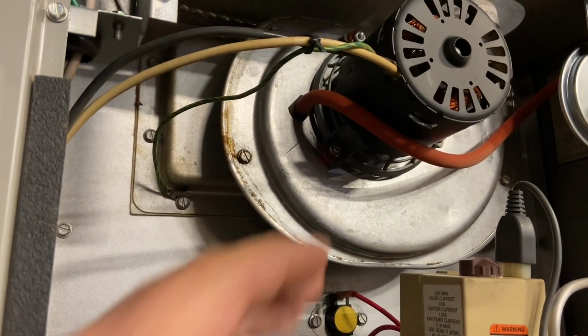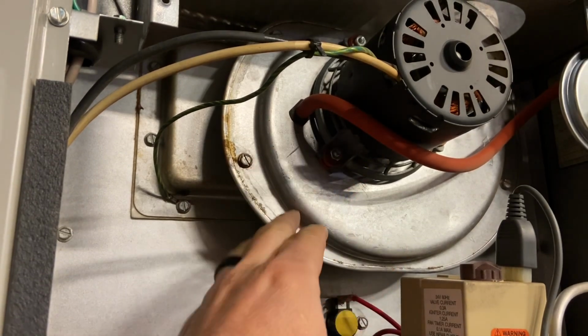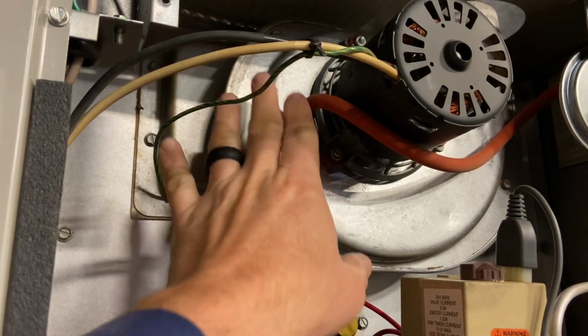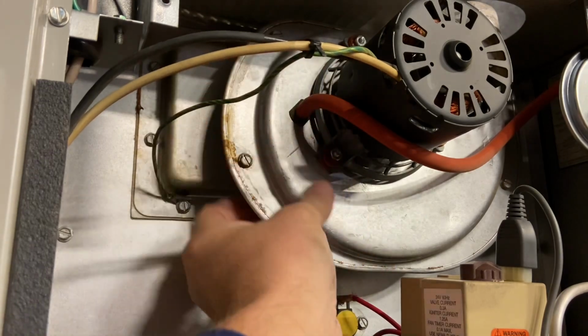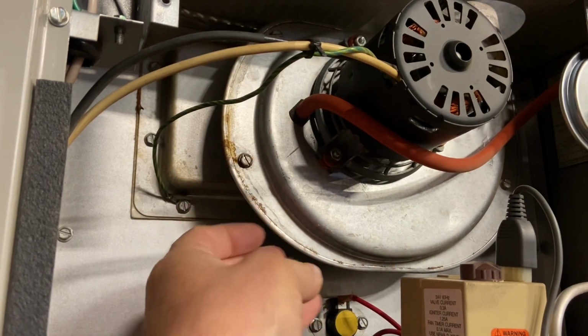The top side here is our inducer fan motor. This is replaced as an assembly. We're going to pull this off shortly, but this motor and this assembly all connects together and it pulls the draft through the heat exchanger.